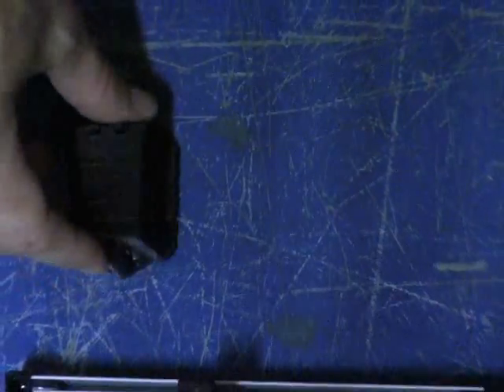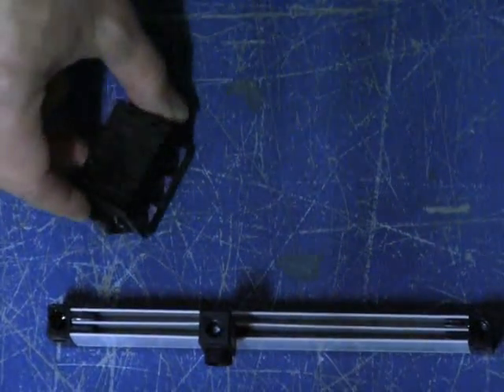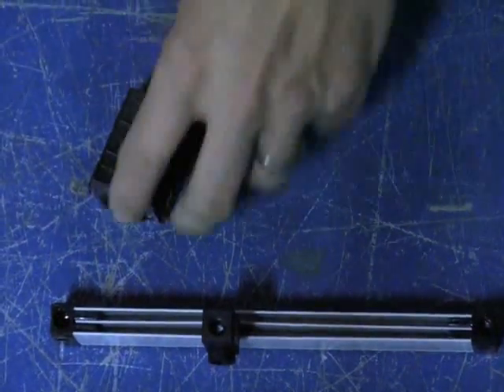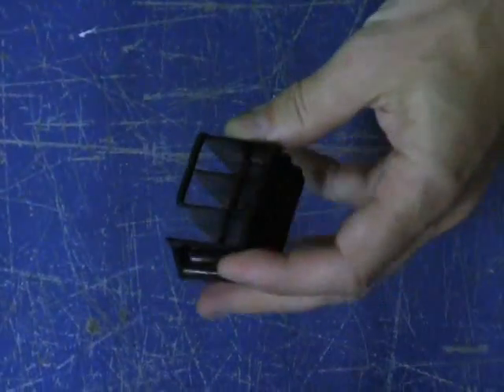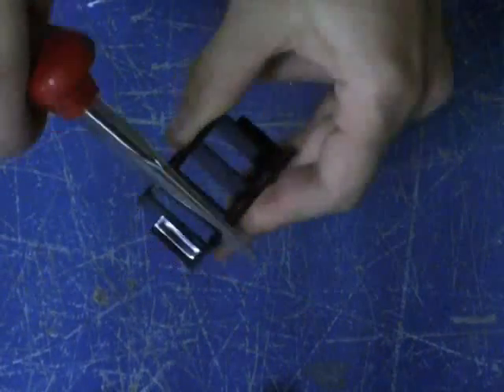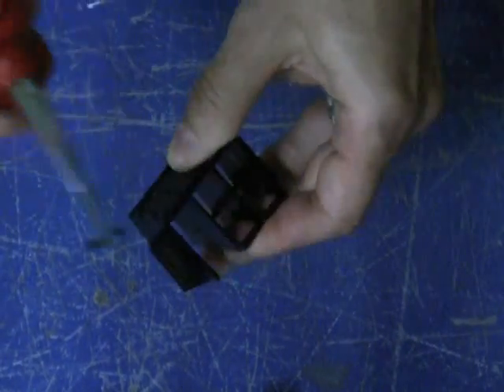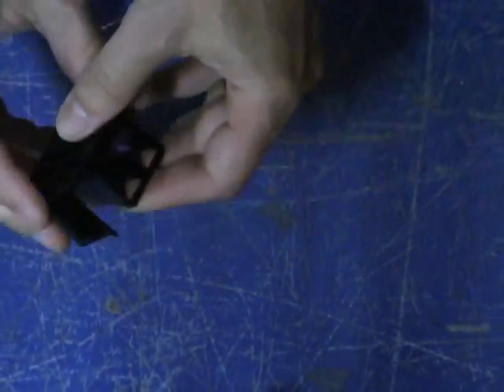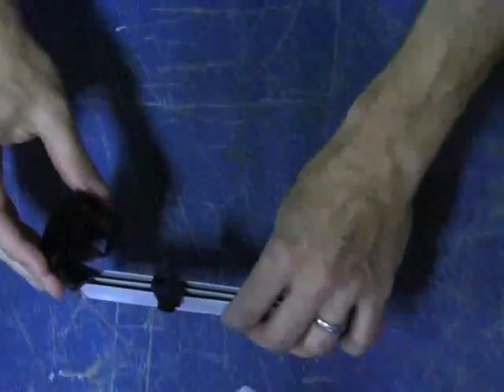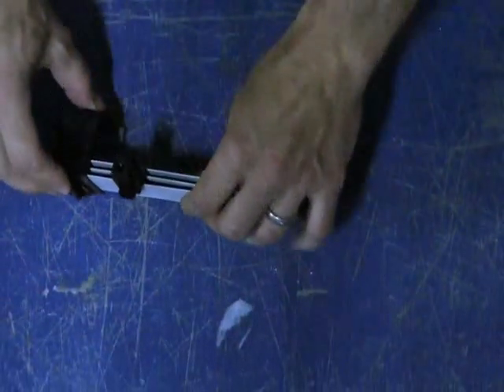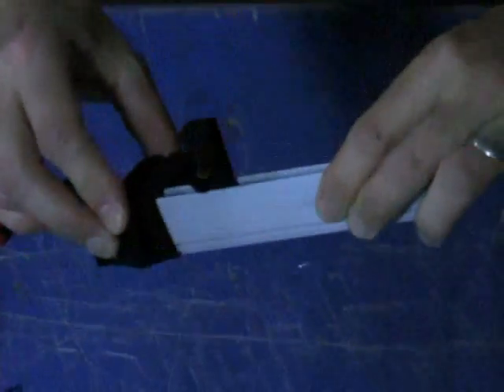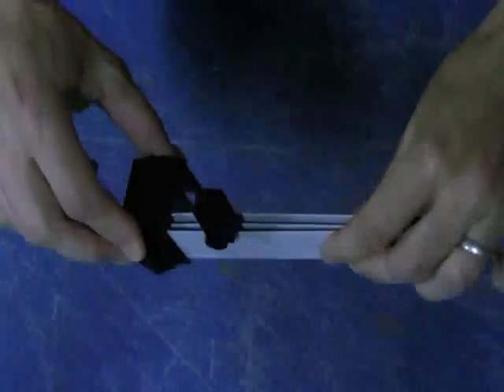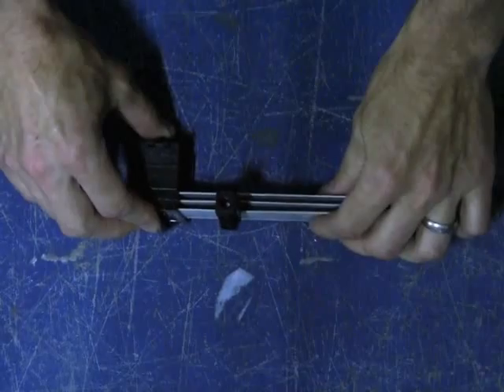The next accessory is the bar holder 19FT3V which holds the APD system in place in a panel. You have to remove breakout tabs for the bar holder to mount the insulation flush with the panel. The bar holder can hold up to three APD system installations or six phases of bus bar.